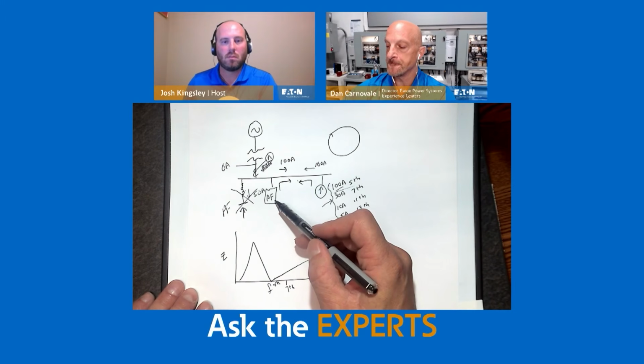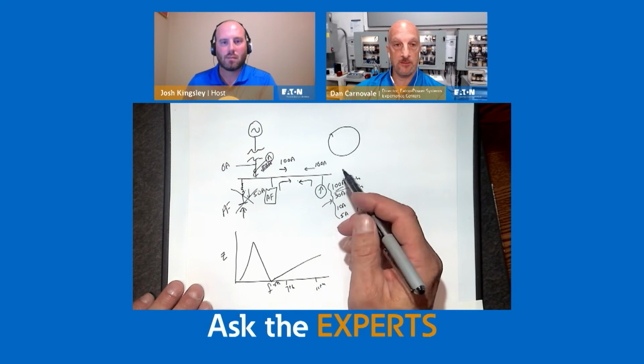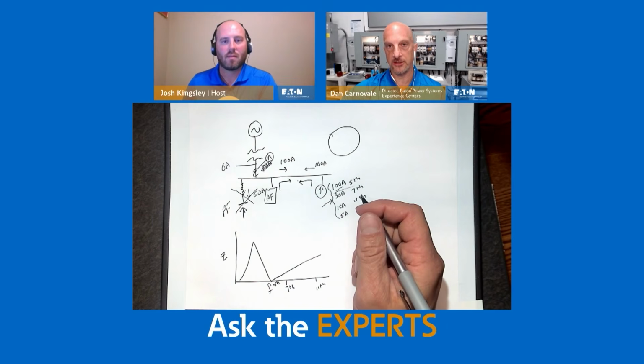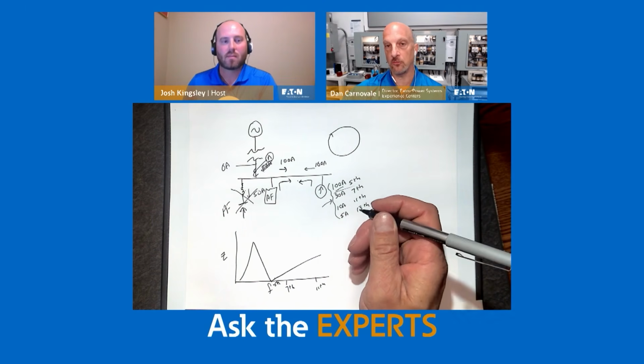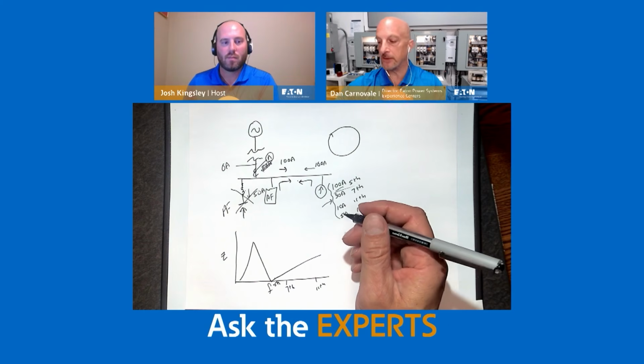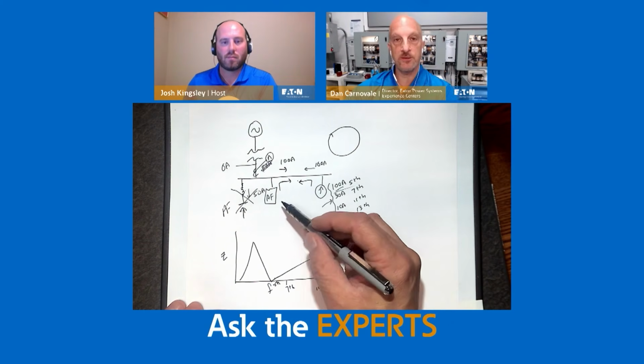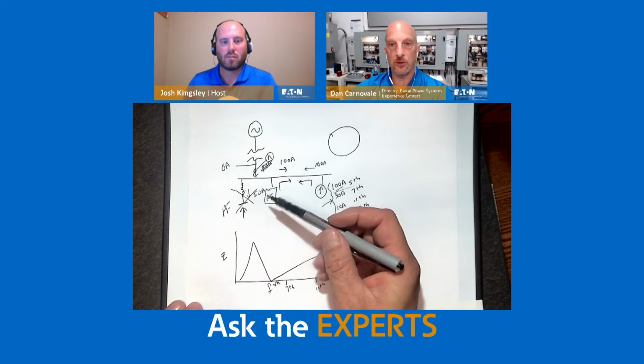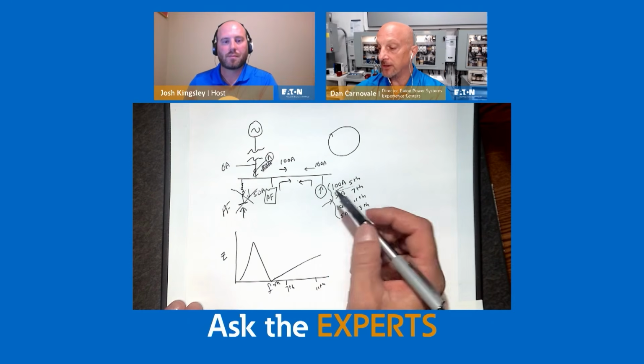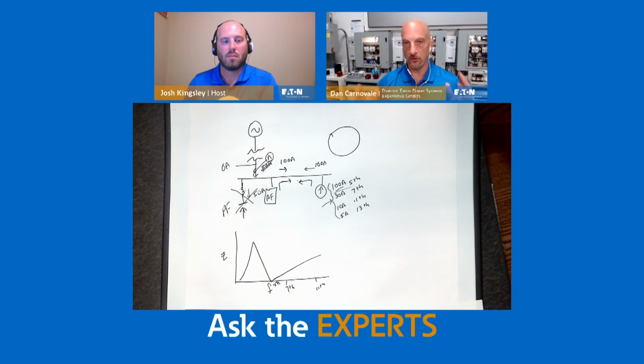So remember going back to the example where we had 10 drives, and 5 of them were running all the time and 5 of them weren't. You don't know which 5 are going to run. So maybe an active filter is still cheaper than putting a single filter or multiple filters on the system. But that kind of gives an overview of how active filters work.